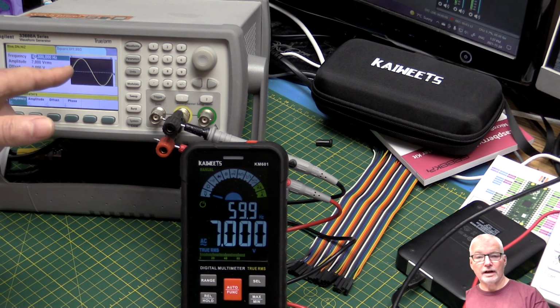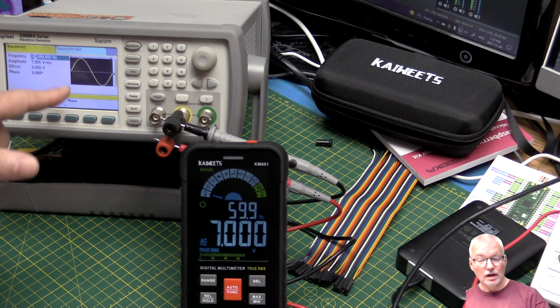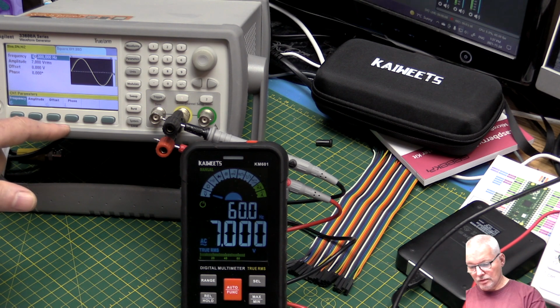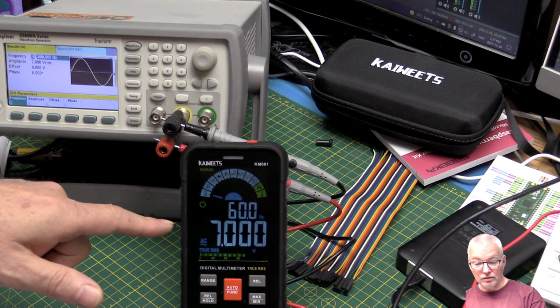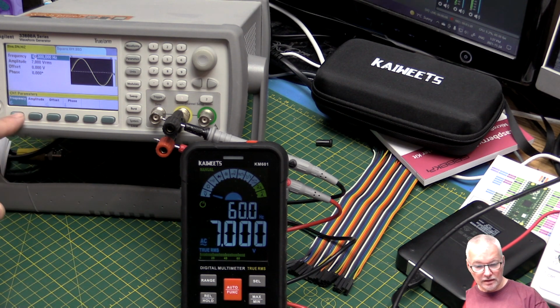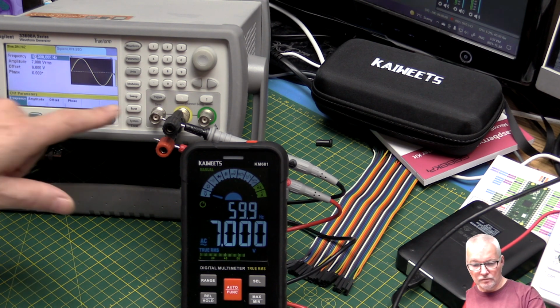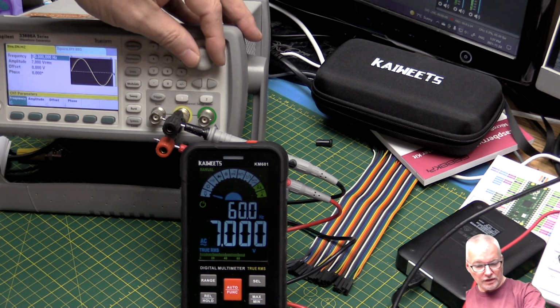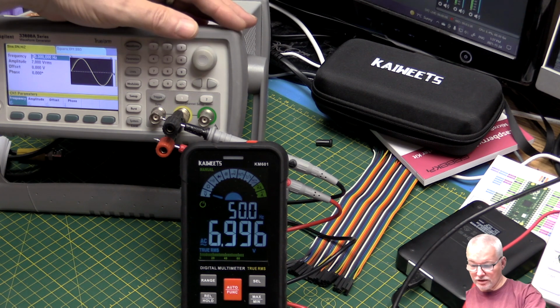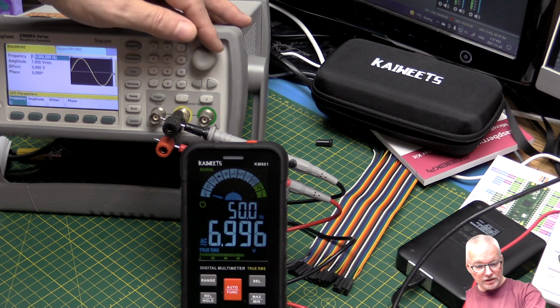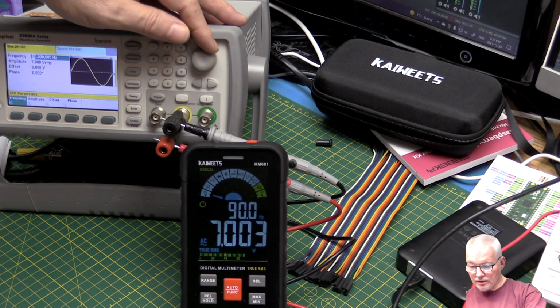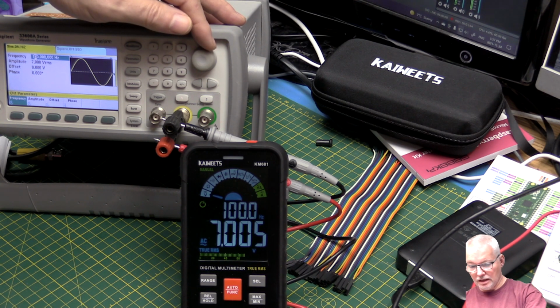So that actually made it slightly more accurate. This is very accurate as far as its output's concerned. It's on high impedance mode. So we're reading 7. I mean, it was pretty accurate before. If I go back to 50 Hertz again, so 50, 6.996, dropped a tiny bit. So let's go up to 100. That's 90 Hertz. There's 100 Hertz. So we're still reading accurate.